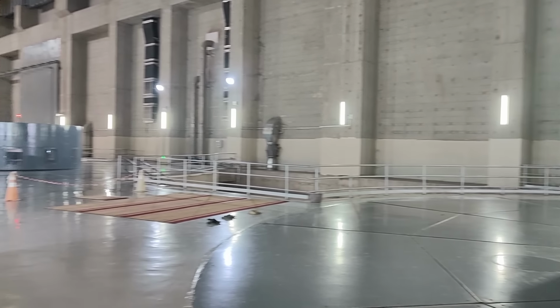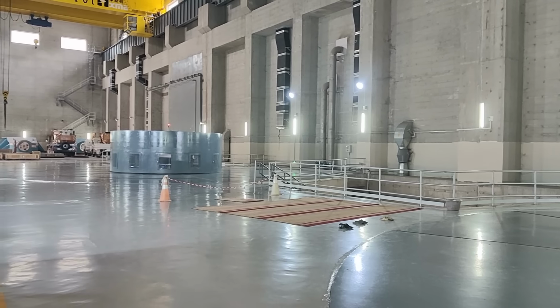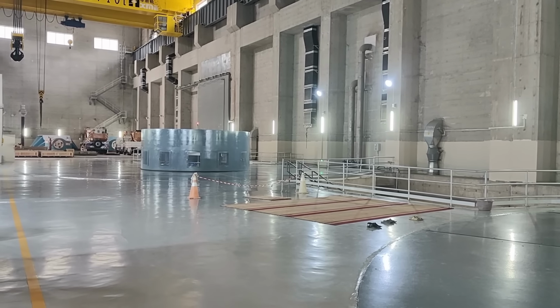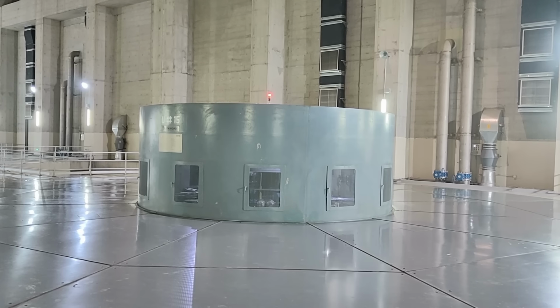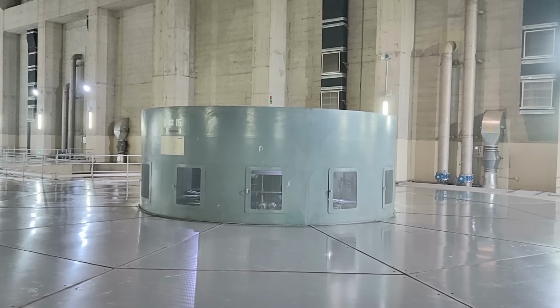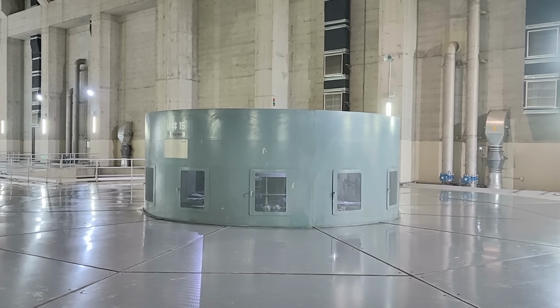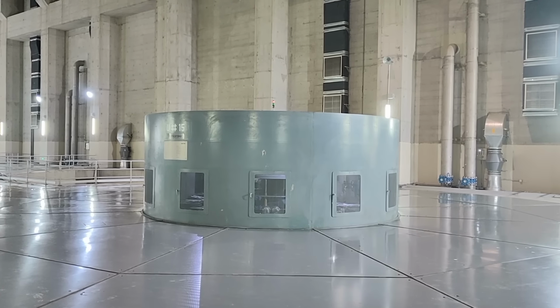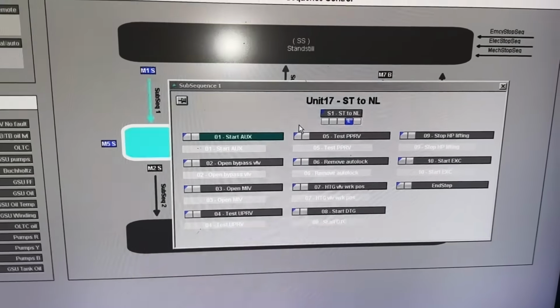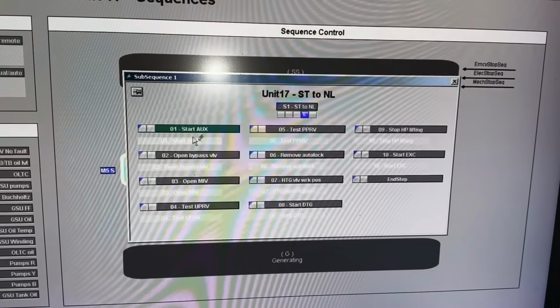But today we are going inside the complete startup sequence of this 470 megawatt hydroelectric unit from total standstill all the way to synchronization with the grid. So this startup consists of 10 major steps before a single megawatt reaches the transmission system. The startup begins from ST condition, which is known as standstill condition.